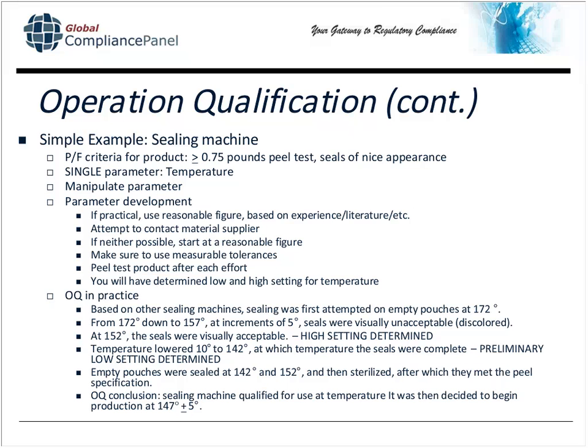And what we do here is, since we've identified that one of our pass-fail criteria is a particular strength of peel test, we're going to peel test after each effort. We're going to make a certain number of pouches at each temperature that we determine, and we're going to peel and peel and peel.